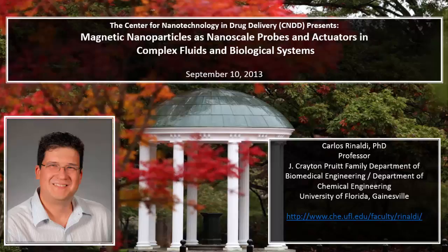This is an illustration of a susceptibility spectrum for the particles, showing that it follows the Debye model. These are measurements of the out-of-phase component at different temperatures, showing that it shifts with temperature. And then you either estimate the viscosity from the peak, or you estimate it from a full nonlinear regression of the whole out-of-phase susceptibility spectrum. And what you get are viscosities, in this case as a function of temperature. In black is the viscosity determined using a rheometer. In red is the viscosity determined from the peak position. And in blue is the viscosity determined from the regression. And in a fairly wide temperature range, the agreement is within 5%.